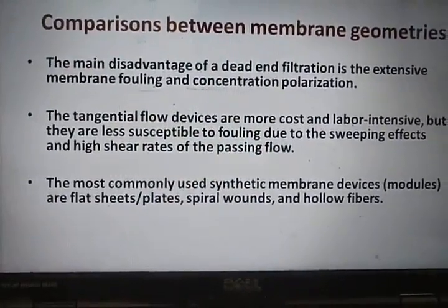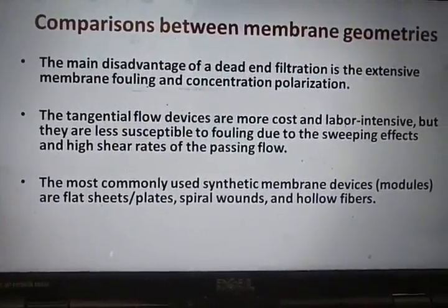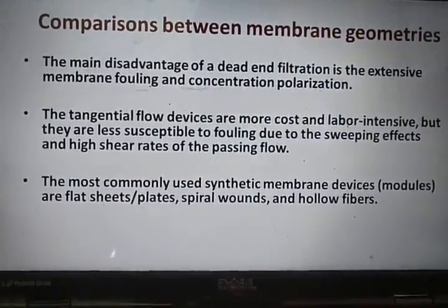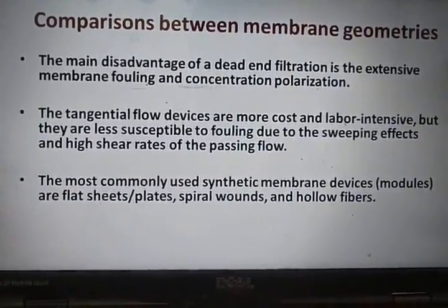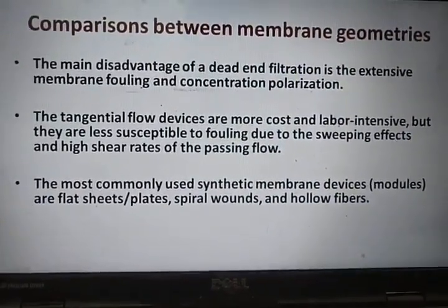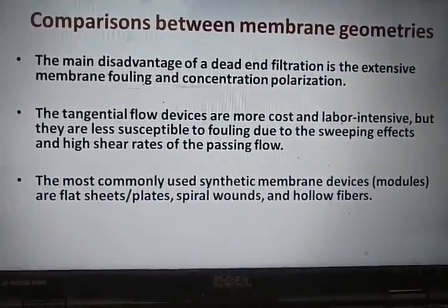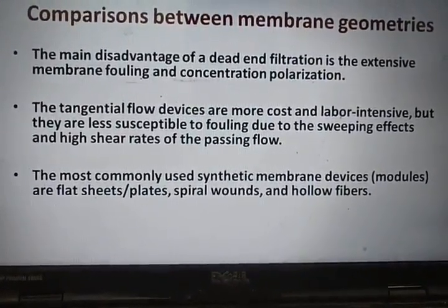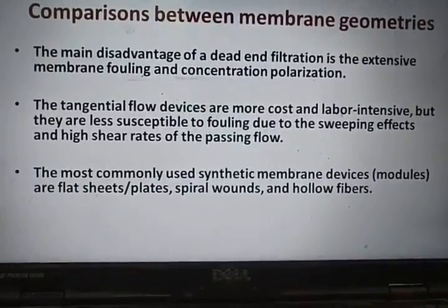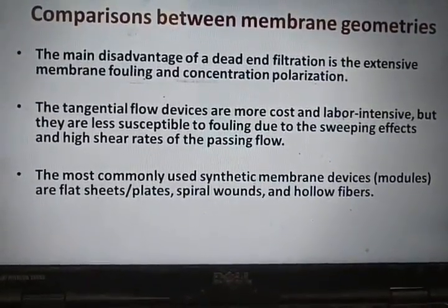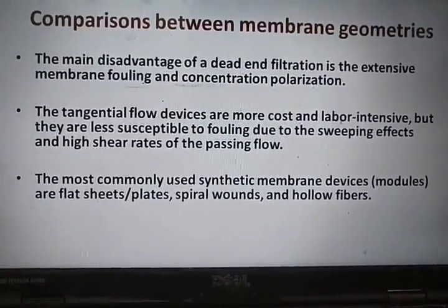Similar to rapid sand filtration, wherein the filter particles get clogged due to the impurities present, here if you talk about membranes, we call it membrane fouling. Next, the tangential flow devices are more costly and labor intensive, but they are much less susceptible to fouling due to the sweeping effects and high shear rates of the passing flow.